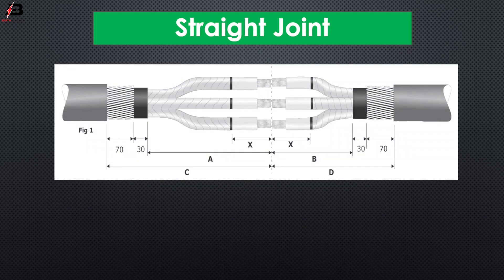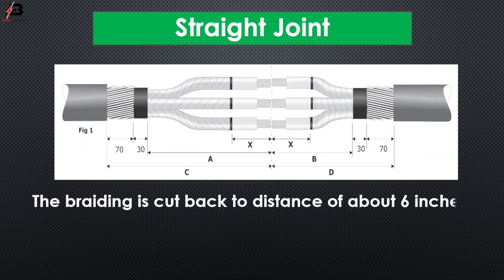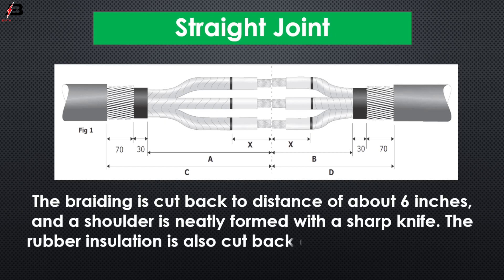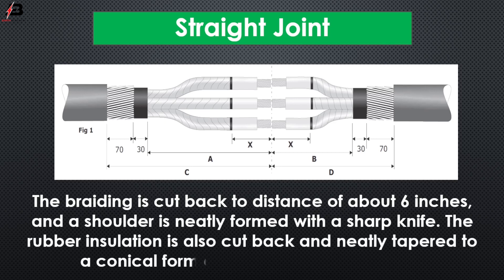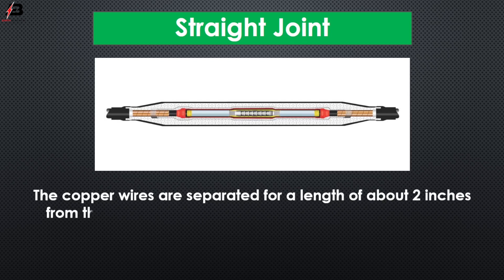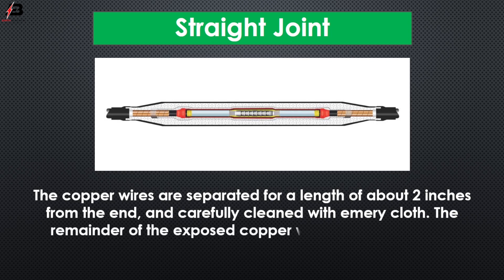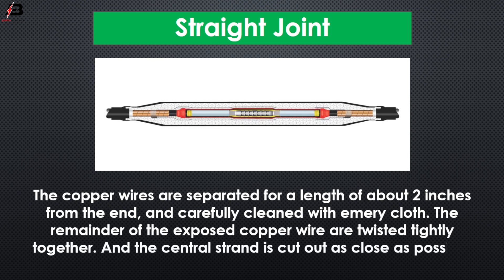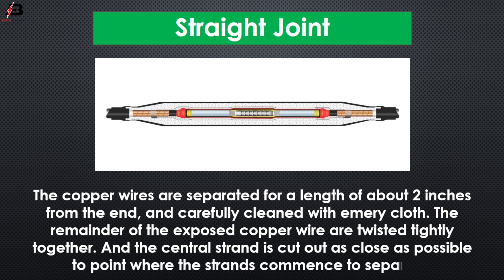Straight joint. The braiding is cut back to a distance of about 6 inches and a shoulder is neatly formed with a sharp knife. The rubber insulation is also cut back and neatly tapered to a conical form about 1 or 1 and a half inches in length. The copper wires are separated for a length of about 2 inches from the end and carefully cleaned with emery cloth. The remainder of the exposed copper wires are twisted tightly together and the central strand is cut out as close as possible to the point where the strands come to be separated.